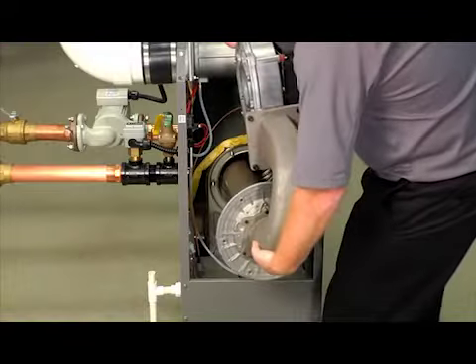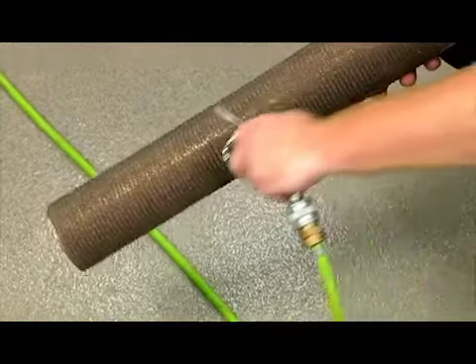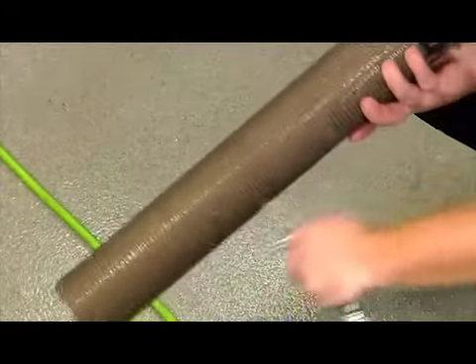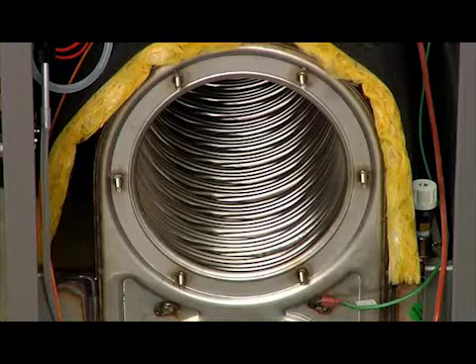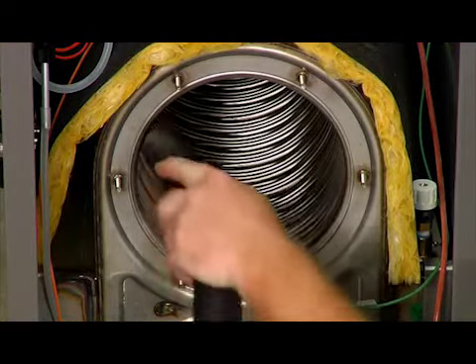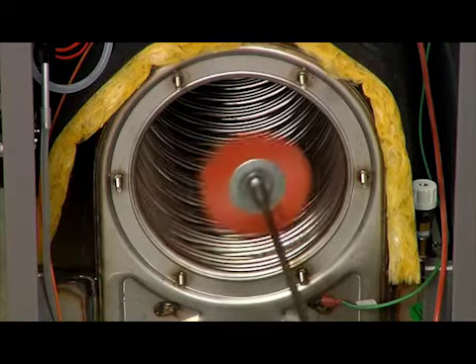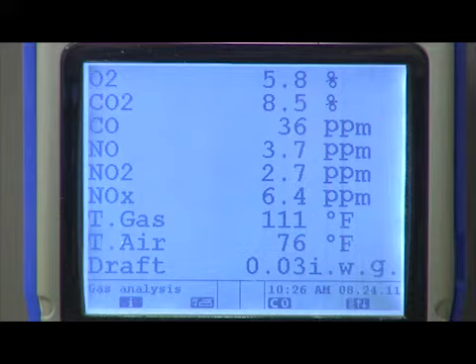Refer to the video How to Measure Inlet Gas Pressure to determine if an adequate gas supply has been delivered to the unit. Refer to the video Burner Removal and Cleaning to determine if the burner is damaged or is in need of cleaning. Refer to the video Heat Exchanger Access and Cleaning to determine if the heat exchanger is in need of cleaning. If the CO2 and CO levels are still not within the specified ranges after reviewing the possible causes, adjustment of the gas valve may be necessary.